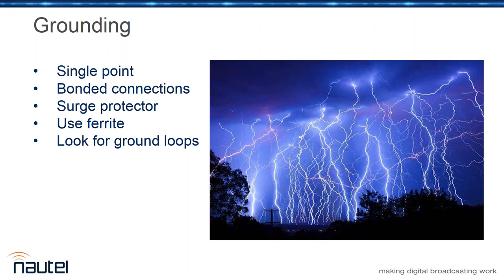So in that case, what you're doing is working with a voltage divider principle. Look for the lightning energy to follow the lowest inductance, lowest impedance path to ground. Make that the big easy one. Conduit's got a lot of connections, a fairly high impedance relatively speaking, so that's going to be less an issue.